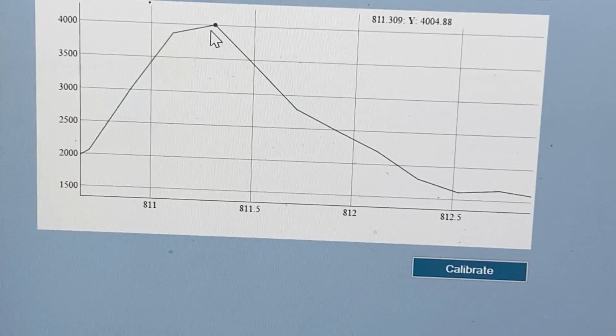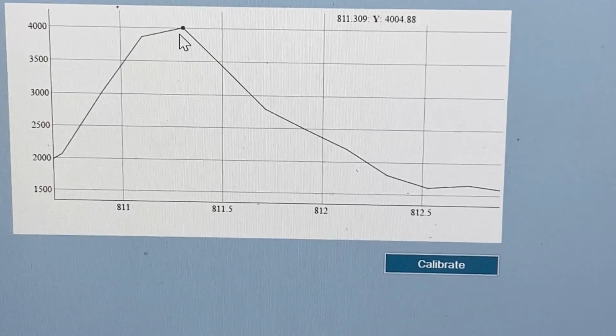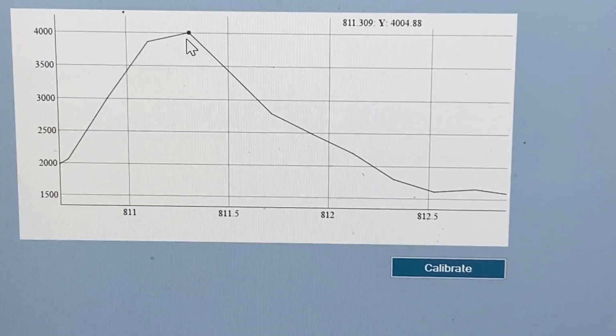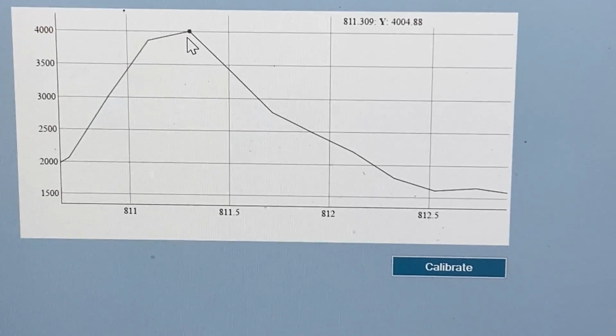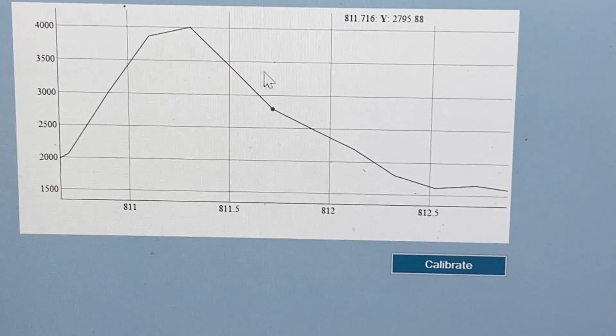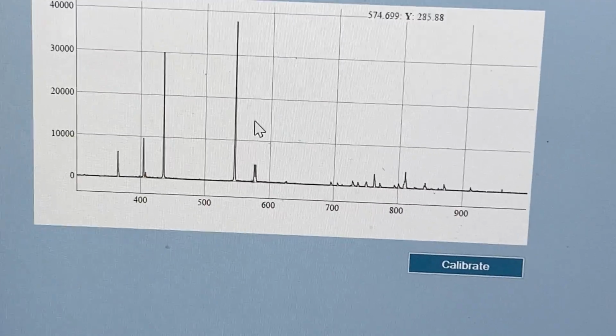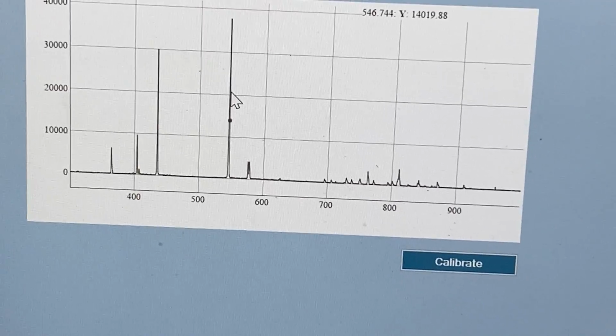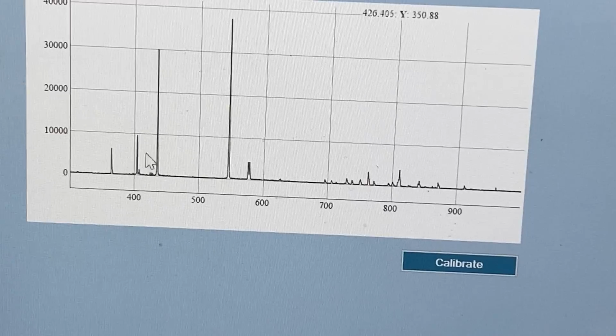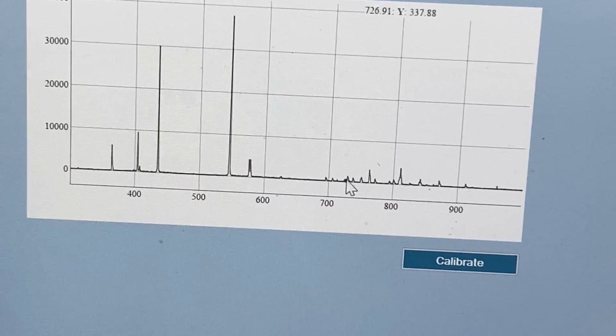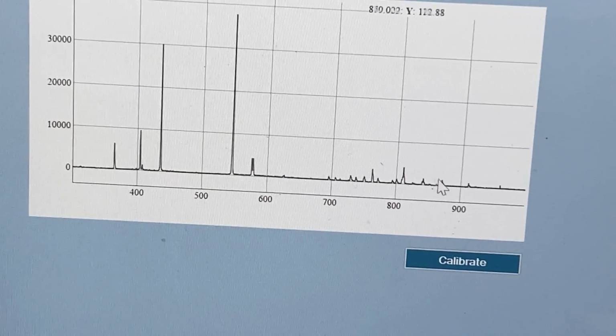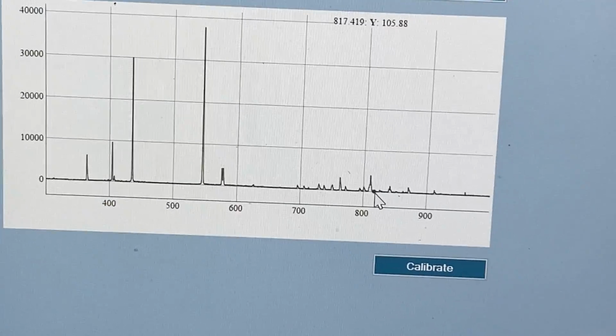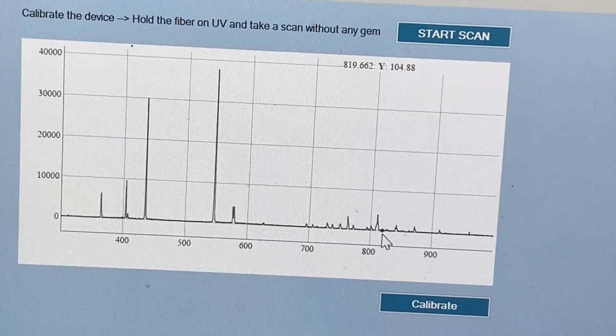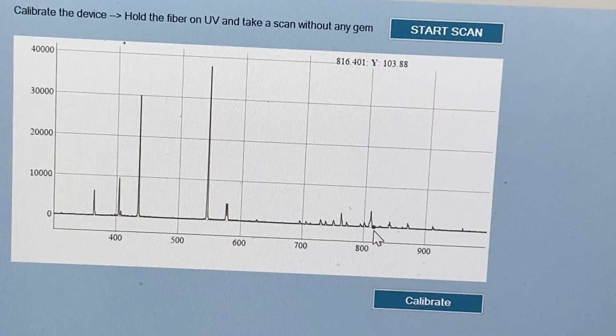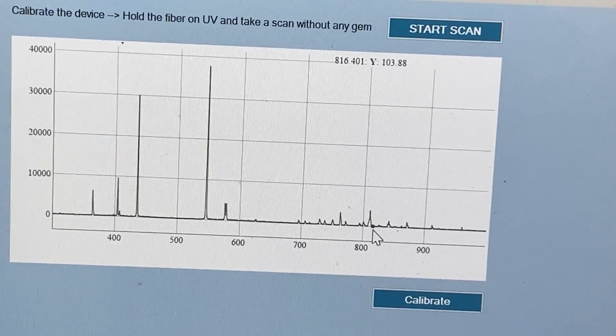Okay, 811.3, and that is supposed to come out 811.5. So there's 0.2 of a nanometer on that one. So there you have it. This is what the spectra looks like, the calibration spectra, and it looks at about 7 of these and calibrates on them to make sure that they're within the 0.2, at most 0.3 of a nanometer.